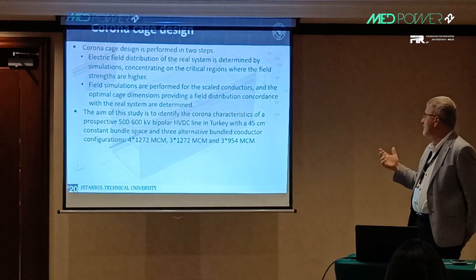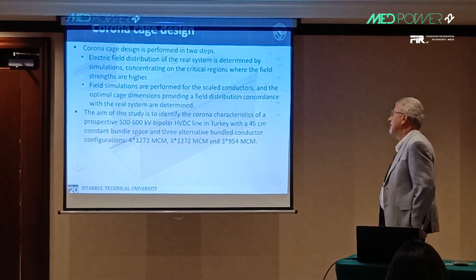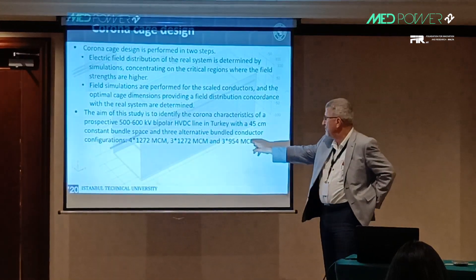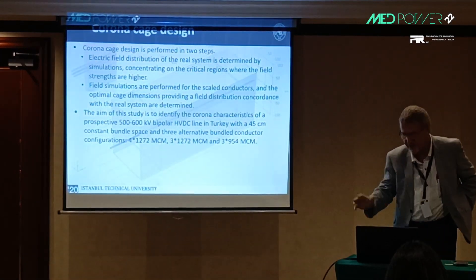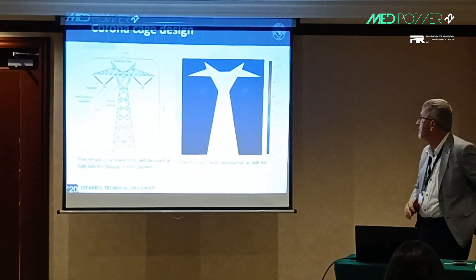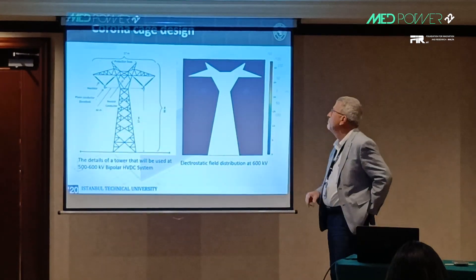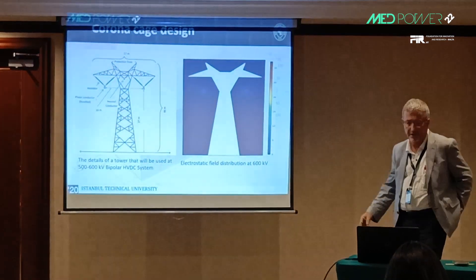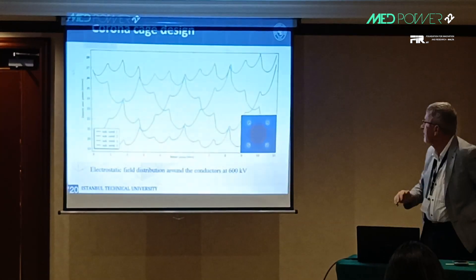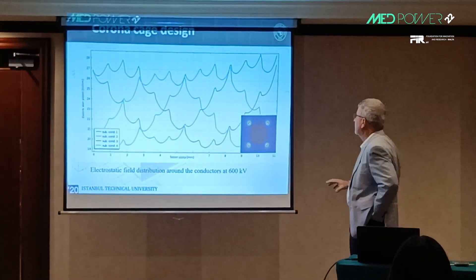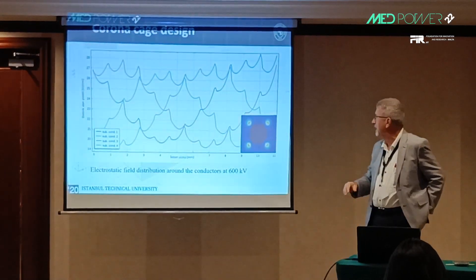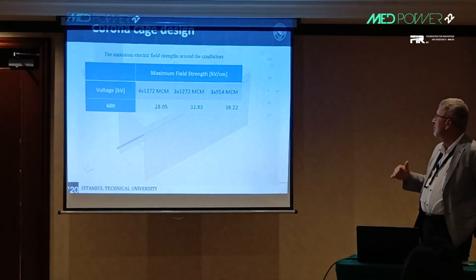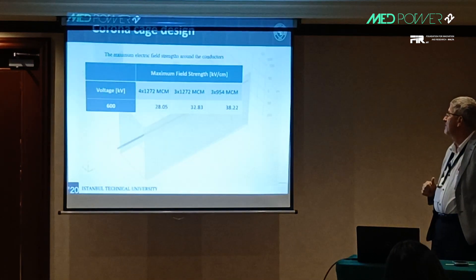The aim of the study, as we said before, is to deal with the test of 500 to 600 kV bipolar HVDC lines. We had three prospective conductor geometries, so we performed the tests for those conductor geometries — that is the line for which we want to design the corona cage. On the right-hand side you can see the field distribution of such a tower, and looking closely around the quadrupole conductors gives a better idea about the electrical field strength.